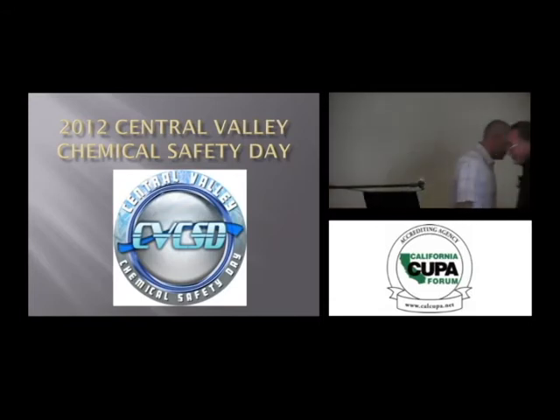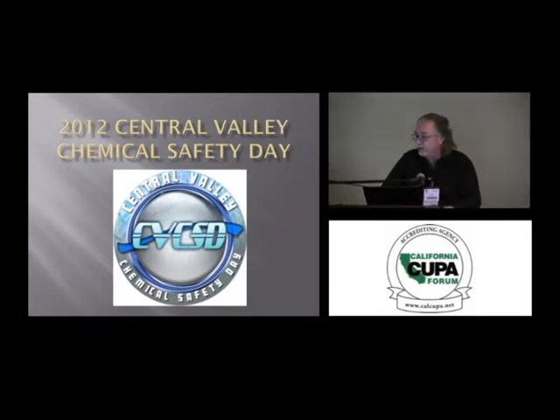Compatible. Well, actually, they've been there for 20 years, so they must be compatible, but they weren't designed for ammonia refrigeration systems. One thing, as an end user that I have been in the past, and an operator, a lot of times our nameplates will get painted over, they'll be insulated over, they fall off, etc. I was also an inspector in the state of Wisconsin. If the thing has been there for 10, 15, 20 years, and I don't see any pitting or very little pitting, I'm not going to condemn that vessel. It's been there, it's proven its life.